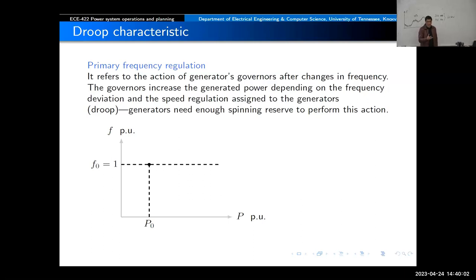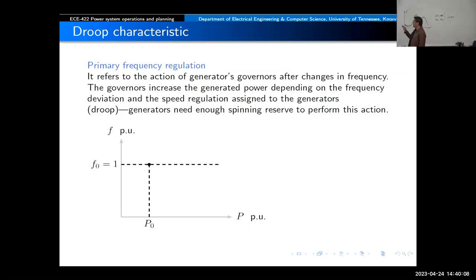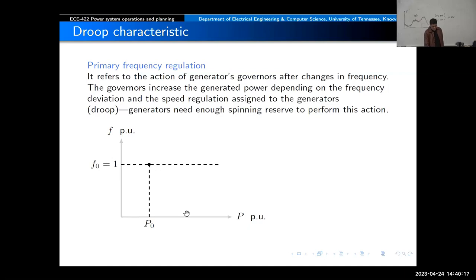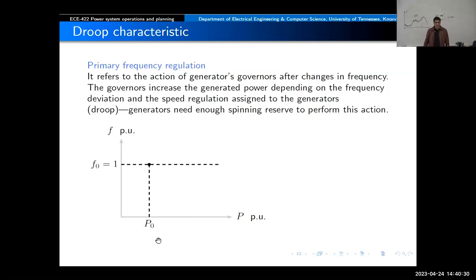Let me start describing the main aspect of frequency control: the droop characteristic. We have generators in the system, and here is a plot of frequency versus generated power. At a particular operating point, we assume the frequency is at nominal — one per unit, 60 hertz. The power P0 generated at that point is determined by economic dispatch: we decide the cheapest option and assign what power the generator will produce.